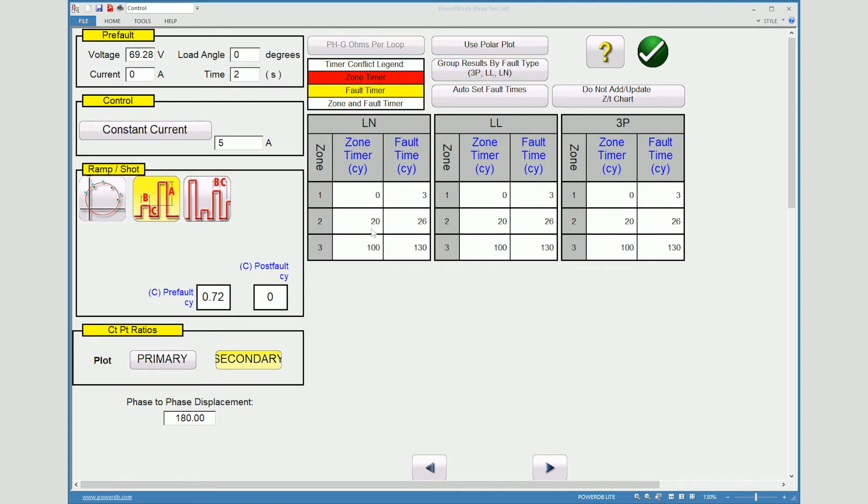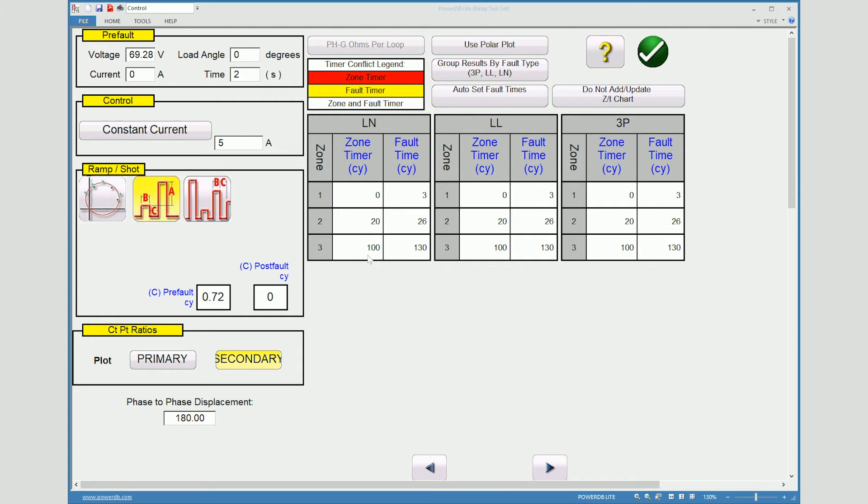Zone two, you will notice there is a 20 cycle delay here. We will pulse that fault for a little bit past the zone two timer. But also it will stay within the zone three timer. So that way it will allow our relay to notice if the fault is within our zone or within the next zones. And then we're doing the same thing here for our zone three.